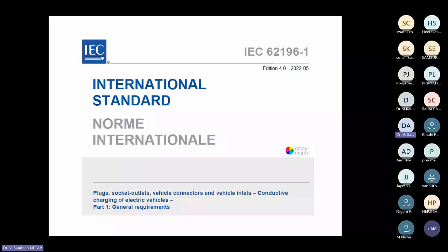Some of the drawings given in the standards show, for example, fast DC charging. You take the power supply from AC, usually with primary rectification and power factor correction built in, then you get a non-regulated DC that is converted to AC by an inverter, using an isolation transformer, then secondary rectification gives you a regulated DC connected to the battery. Look at this: this whole part is outside the vehicle, meaning it's an offboard charger, and only the battery is inside the vehicle.